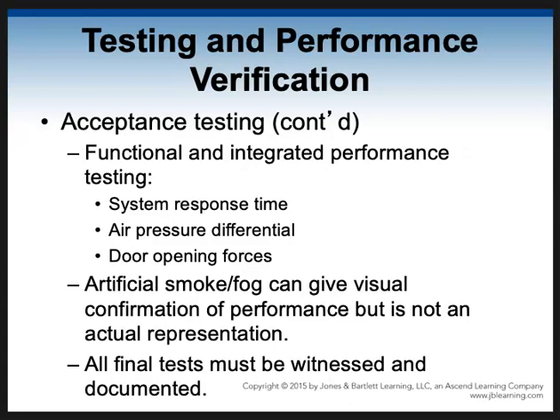The functional and integrated performance has to be tested. Does it respond in the time it's supposed to? Does it pull out the smoke the way it's supposed to? Do the doors open and close the way they're supposed to? It's not just is the air moving, but is all the integration going on? Do the doors close that are supposed to close? Do the dampers close that are supposed to close? Does the HVAC turn off or on, whatever is required? Sometimes you use artificial smoke or fog to help visualize it, but it doesn't actually prove that it works.